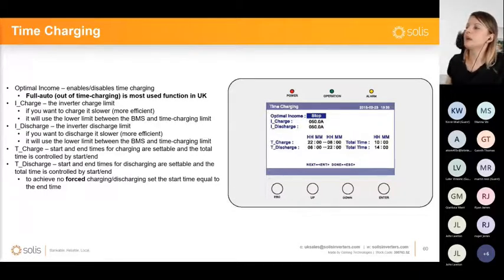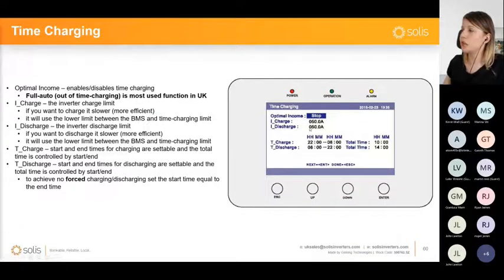So the first thing is the optimal income function, as we call it. It can be either on stop or on run. If it's on stop, then all these settings below are not applicable, so the time of use function is not enabled. But once you put it on run, then all of these will apply. What you are able to change over here is the maximum charge and discharge current that you are allowing the inverter to charge or discharge the batteries. So this is just force charging.